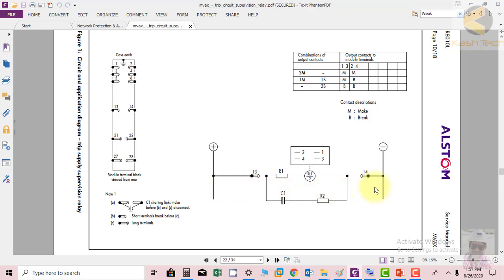It's monitoring only the breaker when the breaker is in closed position. So it has only one coil, and it does monitoring only when the breaker is closed. This is the coil of MVAX 11, and when the breaker is open, this relay is not monitoring. Normally it is most important to monitor the breaker tripping coil status when the breaker is closed, so this is a somewhat cost-effective solution that can also be used.